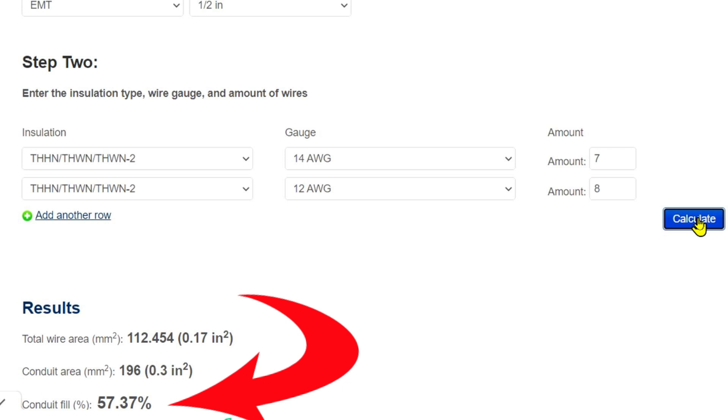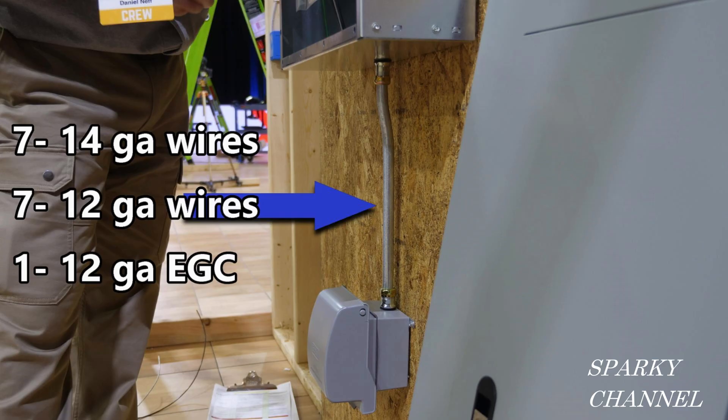So because it's less than 24 inches, that is what we call a nipple. The EMT nipple is less than 24 inches. We can fill it up to 60%, and it comes out at 57.37%. Of course, I don't recommend stuffing a little EMT like that with so many wires, but I want you to be aware of the code.